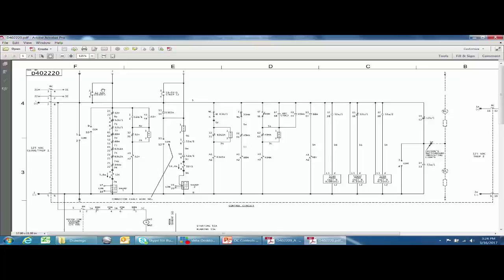Notice there's no mechanism within this circuit to de-energize and reset it. The only way to do that is to remove DC by opening up that push button, or in normal operation, by relieving the standing close from your control building. Picture a substation operator holding a control switch closed — the breaker closes but closes into a fault. You might hold that handle for a second or two, which is an eternity on the grid — enough to possibly collapse the voltage on your system and lead to a regional outage. This anti-pumping scheme prevents that and makes the breaker trip free.